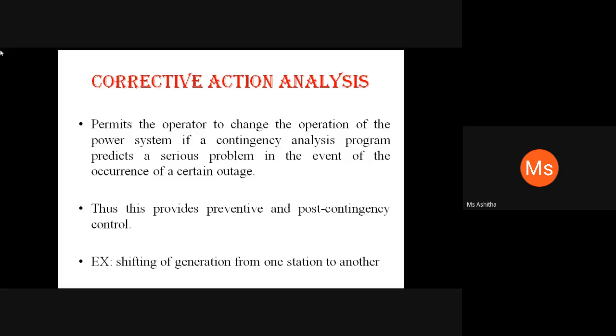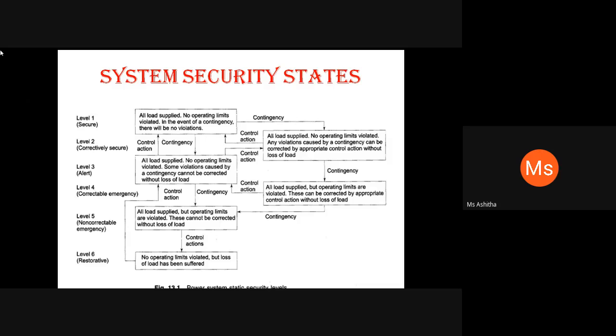And the third major security function is corrective action analysis, which permits the operators to change the operation of the power system if a contingency analysis program predicts a serious problem in the event of certain outages. So this provides preventive and post contingency control. A simple example is shifting of generation from one station to another station. This may result in a change in the power flow, causing a change in the loading of the overloaded lines. So these three functions together consist of a very complex set of tools that helps in the secure operation of the power system. So let us see what the system security states are.